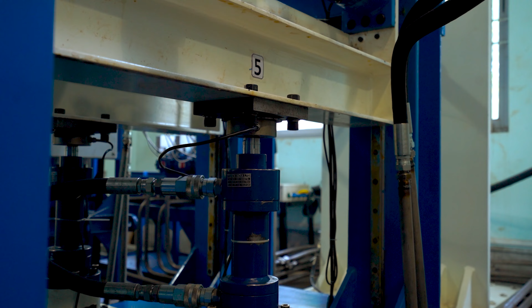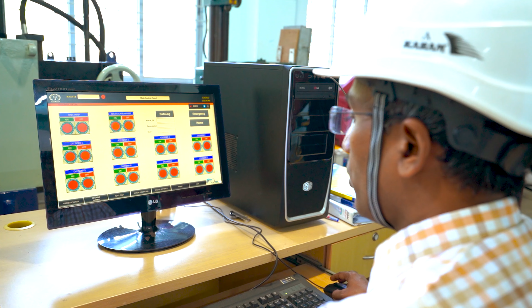Within this machine, this is the VFD panel which controls the motor which rotates the hydraulic pump, the variable displacement pump. Now over here, these modules are receiving the signals from the 8 LVDTs, 8 load cells, and a whole lot of other sensors which are there in the hydraulic power pack. So once these signals are received, then the processor is using it in order to do the closed loop control and also to monitor all relevant variables within the system.